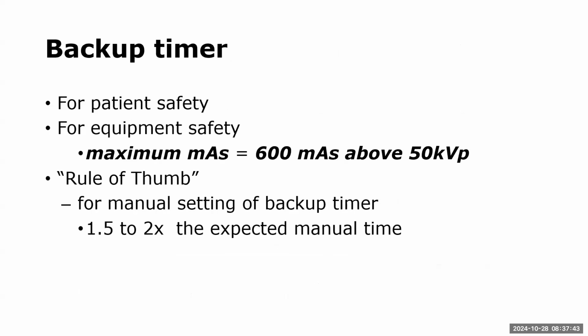Okay, so backup timers. If your equipment has the ability to set a backup timer, that's great, because it can keep you from really overexposing a patient if you make a mistake. It's for patient safety. It's also for equipment safety. Because when I was saying earlier, if I had the wall bucky selected, but I was really trying to do it at the table bucky, in that situation, if my room lets me shoot, look at how many mAs it's going to run up to before it cuts off.